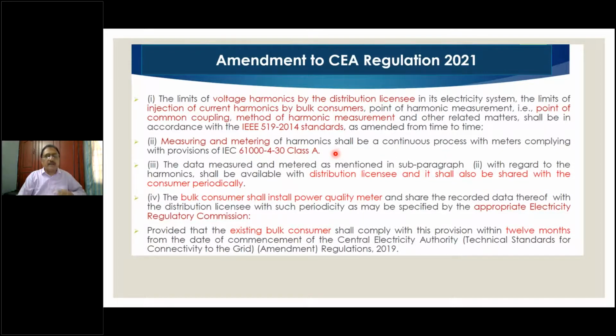IEEE 519 2014 standards, how is it different from 1992? We are not discussing all that here. Time is not enough, and I'm definitely not going to bore you with that detail. So the second thing is, as per CEA regulation, the metering and the method of measurement are discussed as per IEC 61000-4-30 Class A. Similarly, they are also talking about providing a power quality meter permanently installed for measuring harmonics as well as various power quality topics.